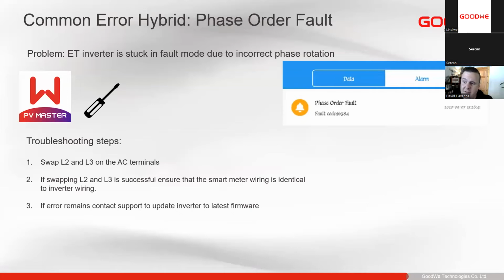The only thing with this one is that it typically creates another mistake, and that is our meter wiring. Everything is wired up, we install an inverter, we install our smart meter, now we're switching on to commission, and we have a phase order fault. We rectify this so the inverter is happy, but we've not rectified it on the smart meter. But we'll show what effect that has a bit later.